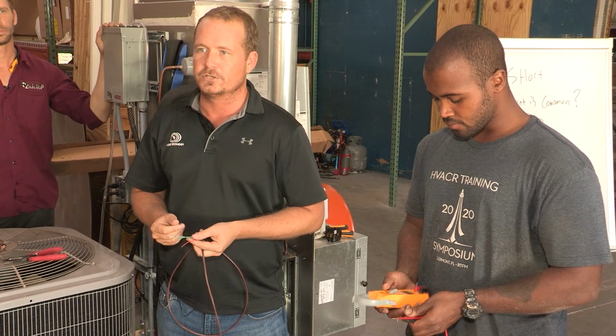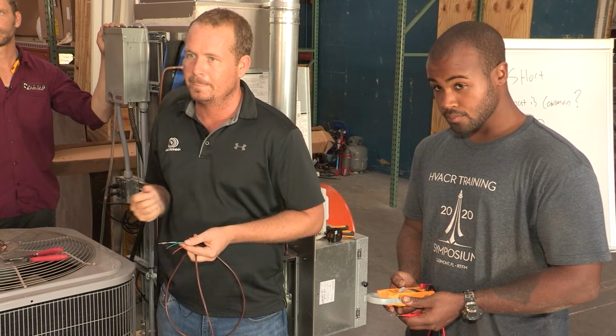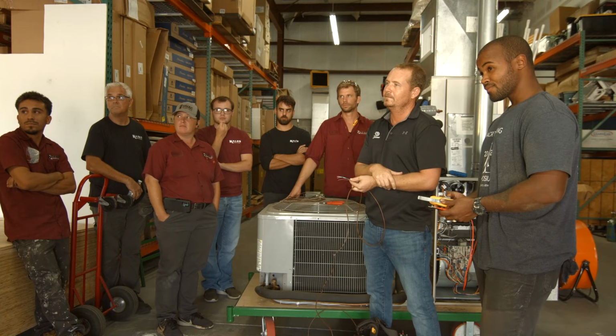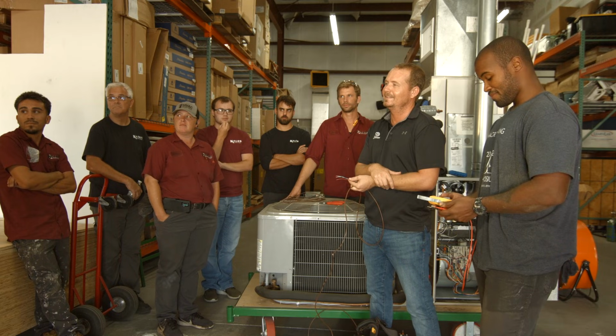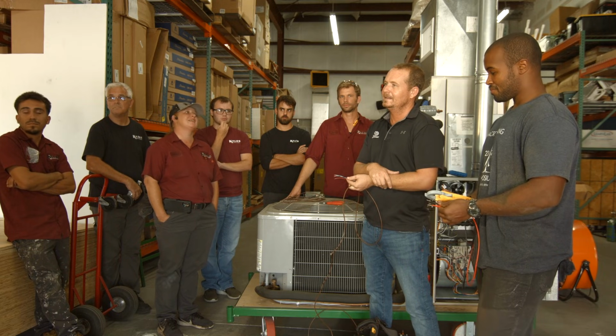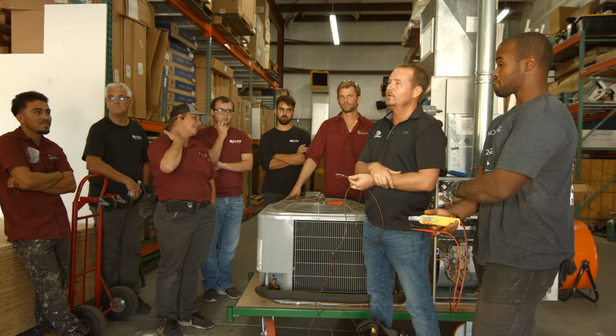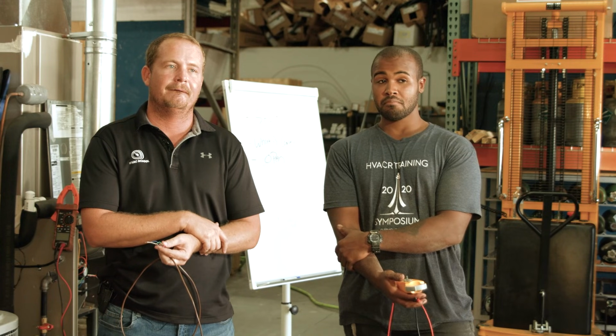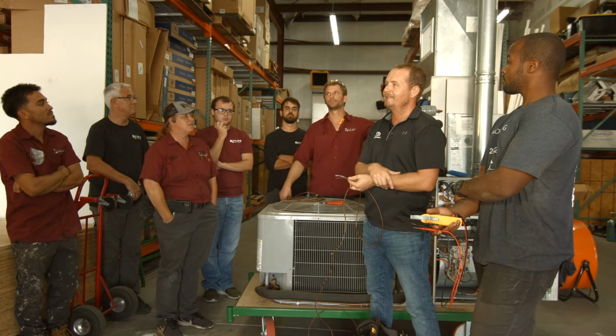But you can also just use voltage to do that. What if I told you I would check that if I had a blowing fuse? Because I'd want to check if my common wire is shorted to any of my other hot wires — without common in the wire nut, you're not checking for an open.